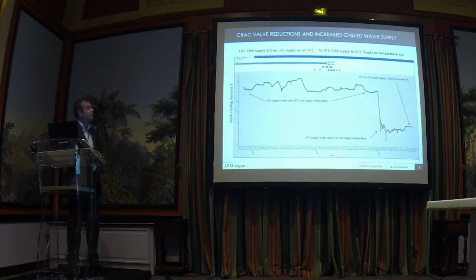So when we start, at 12 degrees supply water into the crack unit, the crack units were set at 20 degrees return temperature. This is the average, 70% just here. This is the average of all the machines. I think it's about 20 air conditioners in this particular data center. And this wobbling here is the temperature of delivery to the crack units varying because the chiller was changing over or something else in the plant started up, and the supply water got a bit hotter because all the crack units are running at 100%. The moment the water temperature in the crack unit increases, if your machine is running at 100%, instantly your data center begins to warm up.